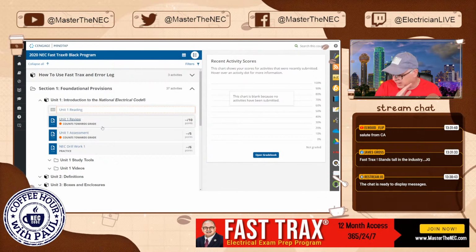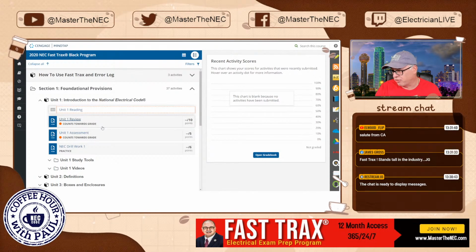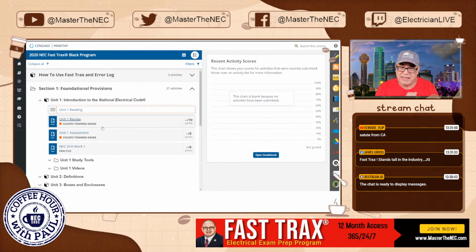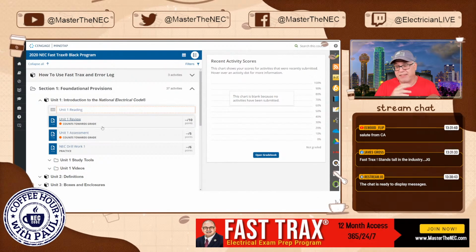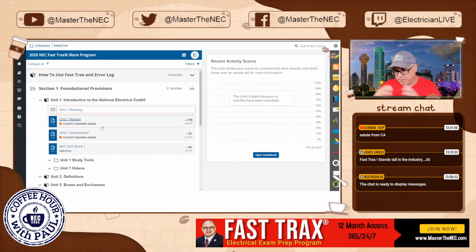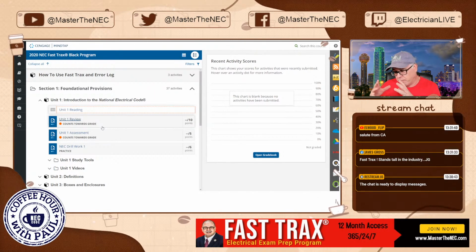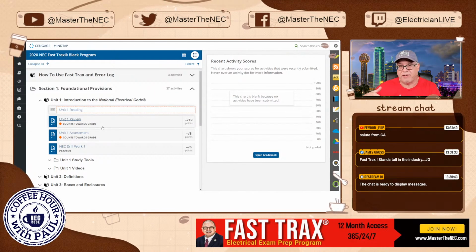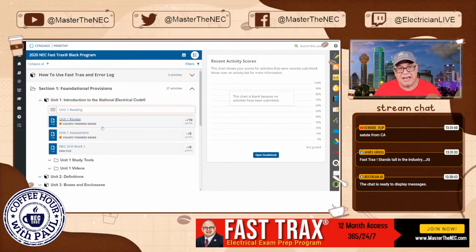And I disagree with that. Okay? I'm not sure that that's necessary, especially in light of the issues that we have with 210.8(F), I guess it's F, dealing with outdoor outlets, not receptacles, that we're talking about, like the point where you take power from the system. So it can be for HVACs and all that stuff. All of that has to be GFCI.